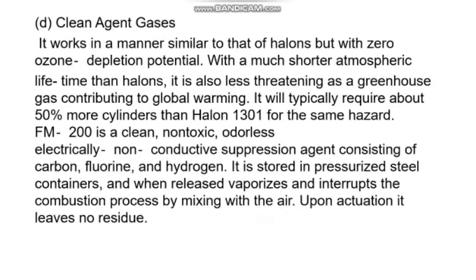Next is clean agent gases. It works in a manner similar to that of halons but with zero ozone depletion potential, with a much shorter atmospheric lifetime than halons. It is also less threatening as a greenhouse gas contributing to global warming. It will typically require about 50% more cylinders than halon 1301 for the same hazard.